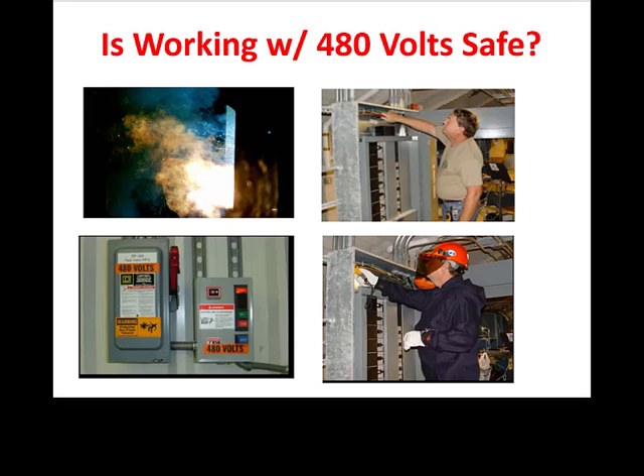So what causes an arc flash in the first place? Faulty equipment or broken down insulation and wiring? Maybe, but highly unlikely. A circuit breaker or fuse continuously tripping out would be a telltale sign you either have an overloaded circuit or other problem with the electrical circuit. Most likely it will be a direct short circuit caused by operator interface, such as touching the electrical panel cover, a tool like a screwdriver, or a test lead on a voltage meter across energized wires, creating a short circuit.